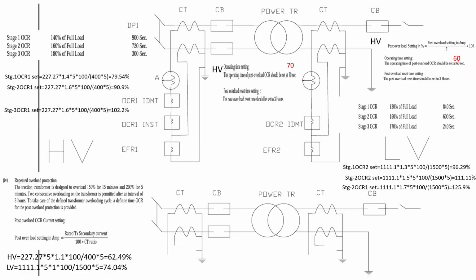How is this system earthing helping? If there is any leakage in the insulation, it will complete the circuit, the current will vary, and it will trip the circuit breaker. So these are all for safety protection: insulation failure, or a dead earth fault near the transformer, will all be caught by the two current transformers. But its restriction is CT to CT: the primary CT to the transformer, then the transformer to the secondary CT. This is the system. So I think you have got some idea about the electrical system.